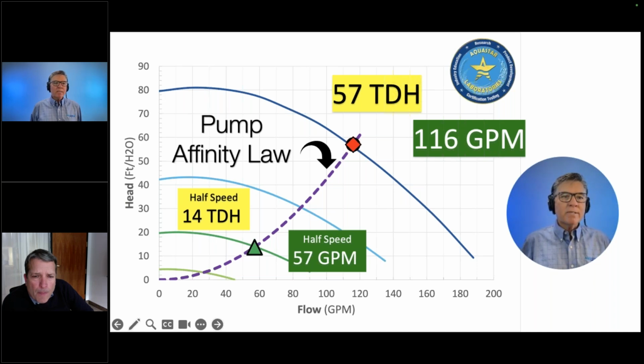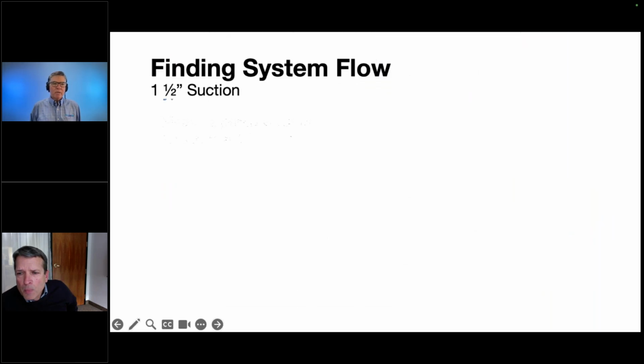The other thing to keep in mind is that pressure is proportional to speed squared. So the speed is going to reduce by half, but the pressure that you see on a filter gauge, for example, is going to reduce by 75%. That's another number that you can calculate. And then the energy savings comes in as power reduces by a factor of speed cubed. So half speed, 1/8 the power. Let me say it one more time: half speed, half flow; half speed, 1/4 pressure; half speed, 1/8 the power. That's why we have variable speed pumps, because of this affinity law. And there's a lot of information on this online.